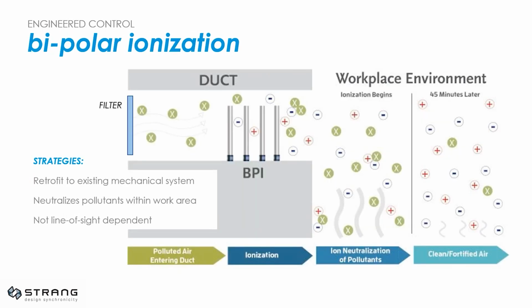Another technology that can be retrofitted into an existing HVAC system is bipolar ionization. Ionization rods are placed within the airflow of your air handling unit after the filters. Microscopic airborne virus pathogens, too small to be captured by the filter, then pass through the bipolar ionization rods. The process causes these ions to become charged and join together and become larger in mass. They're also neutralized in this process, rendering them harmless.